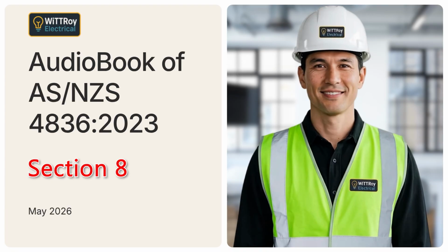Clause 8.5. Insulating barriers, covers, and mats. Clause 8.5 introduces insulating barriers, covers, and mats. These items help separate people from energized electrical equipment. They can reduce the chance of accidental contact with live parts. They are useful controls, but only when they are suitable, correctly rated, correctly placed, and in good condition. A barrier, cover, or mat must not be treated as safe just because it is present. It must be the right item for the voltage, the work situation, and the hazard.